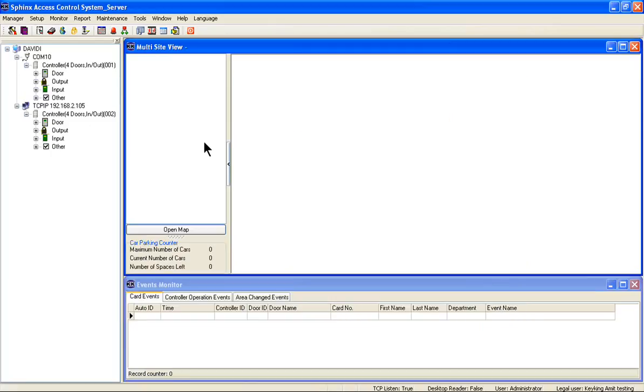Once we set the TCP/IP address, we need to turn the S1 DIP switch of the TCP/IP in all controllers to be off. This is in order to protect from overwriting the existing IP address that we have just set.